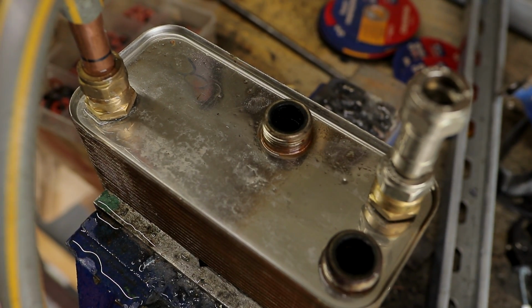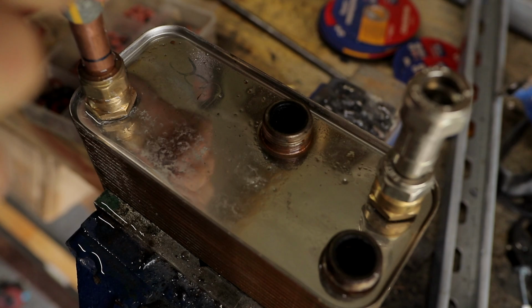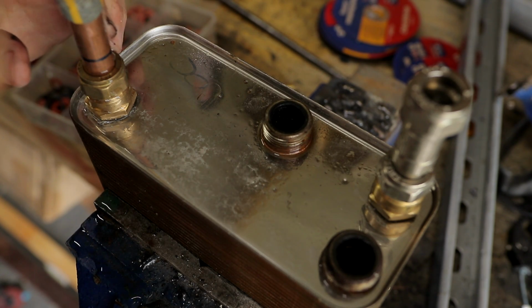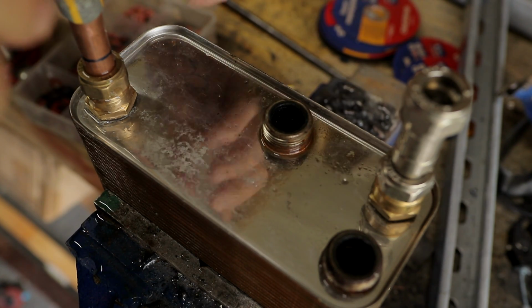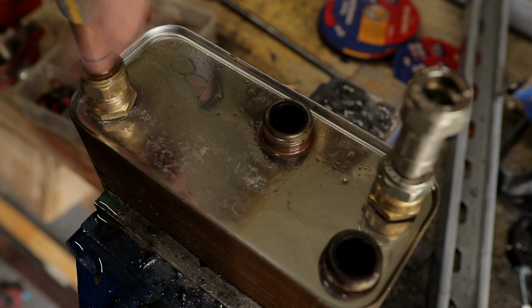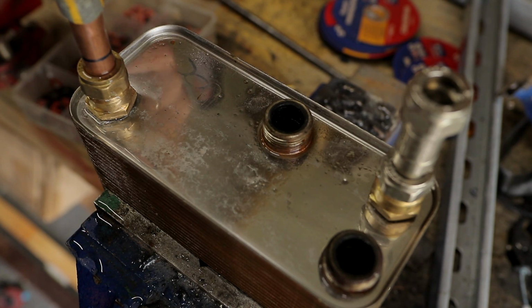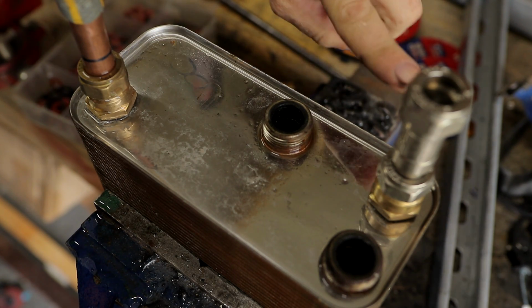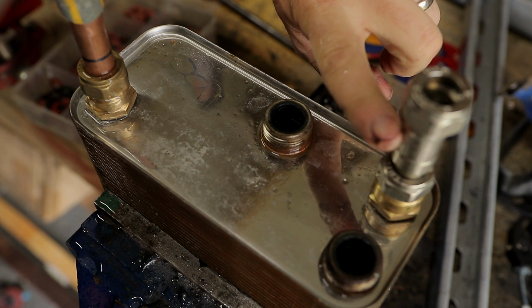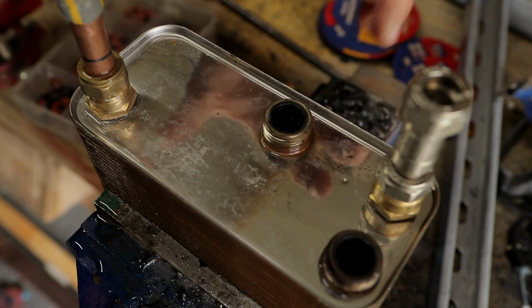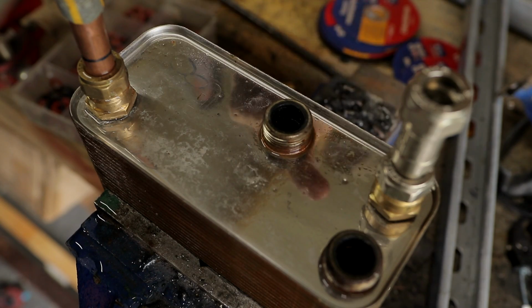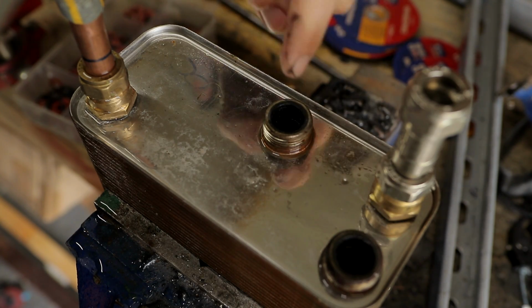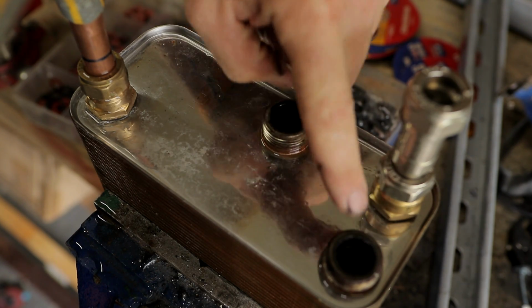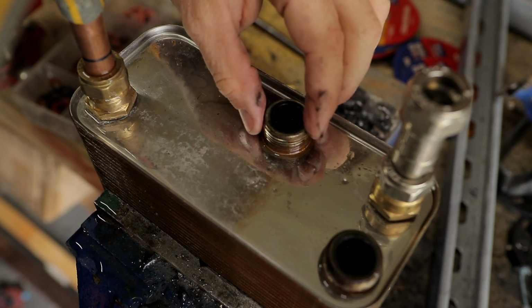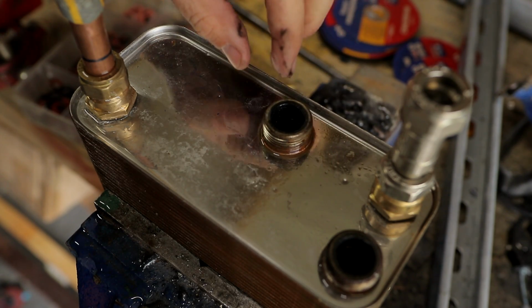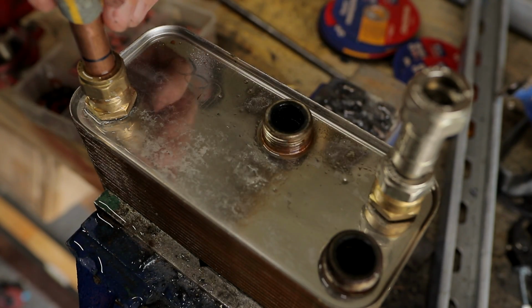Which proves my hunch as to what it was and why I changed this expansion vessel in the first place. So this should be pressurised now. We're letting nothing else into this apart from cold water from the mains, which, because this is shut, should pressurise up. But if there's some sort of problem, if these two have been breached to these two, that would result in water coming out of one or both of these holes, and also that would result in the boiler pressure going up like it was, creating those symptoms we saw.